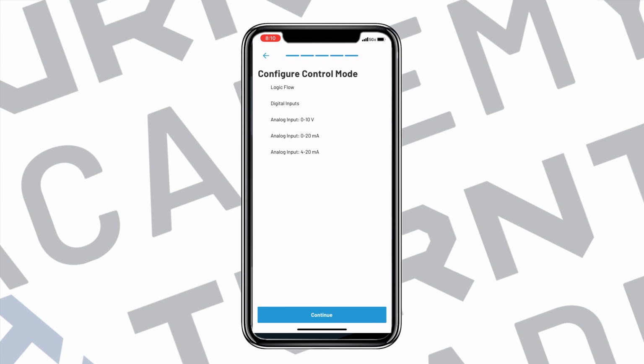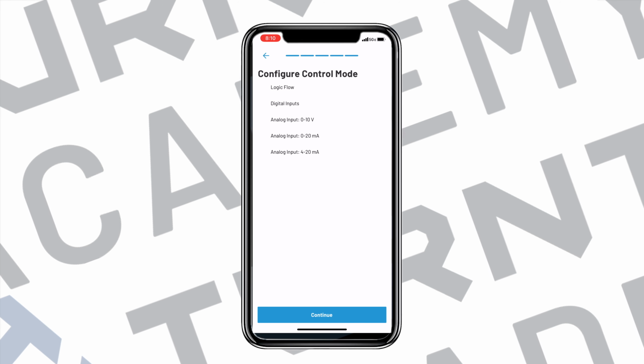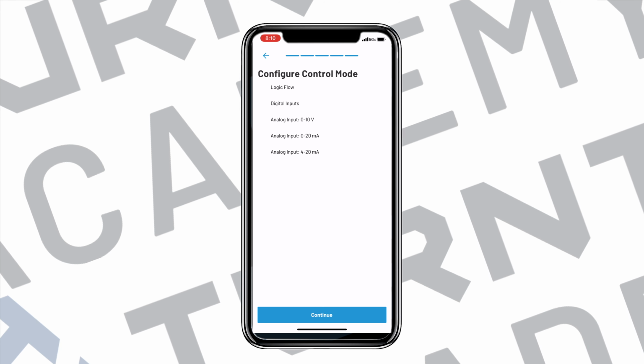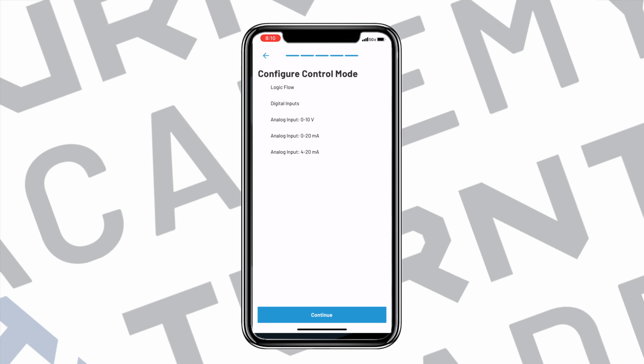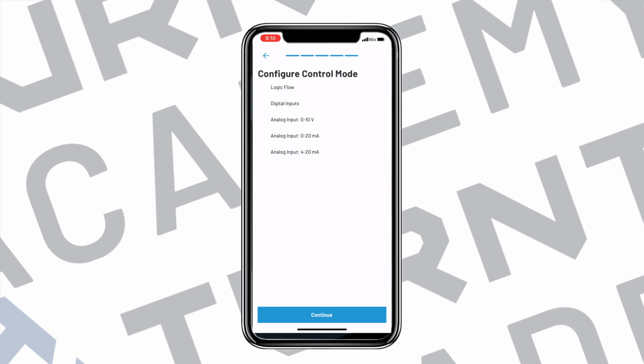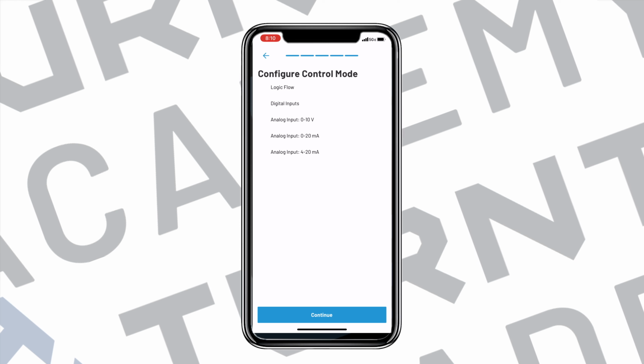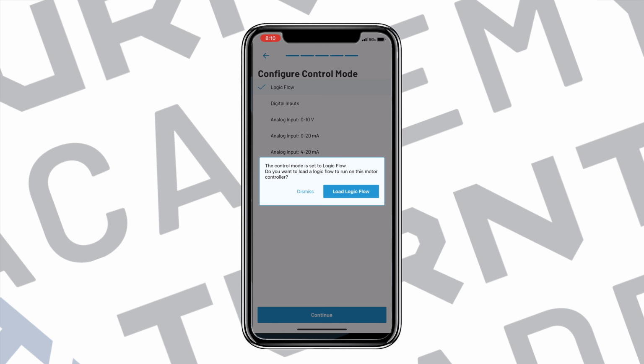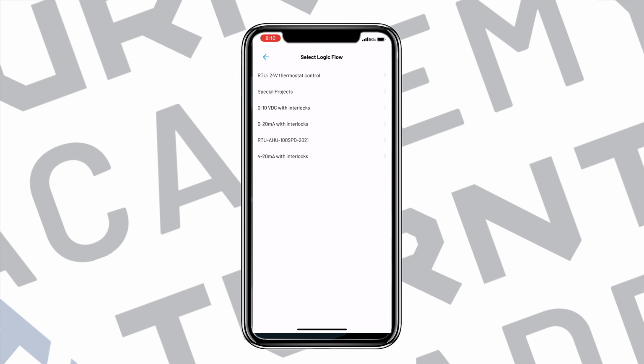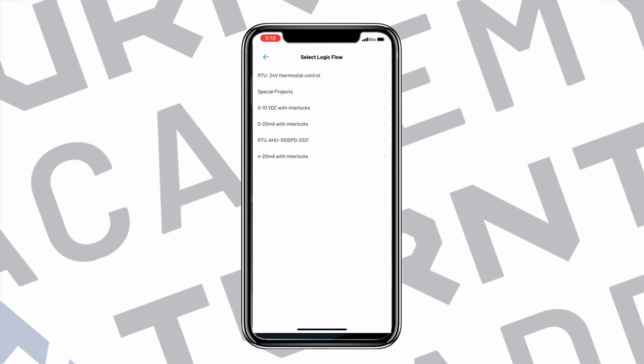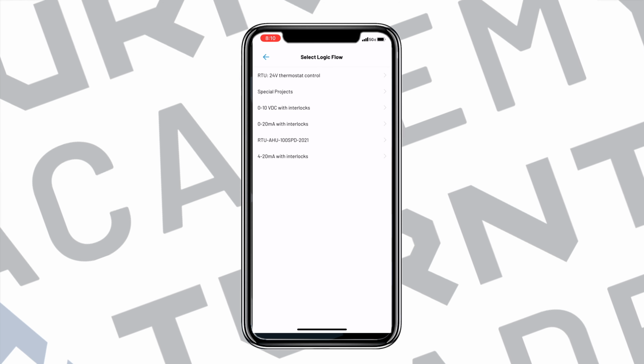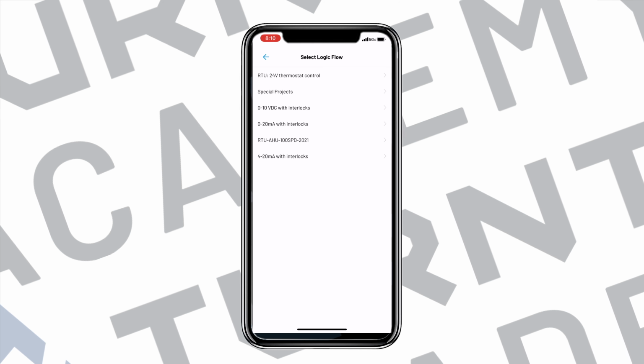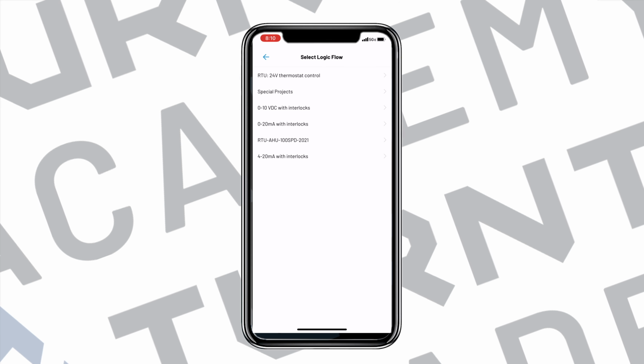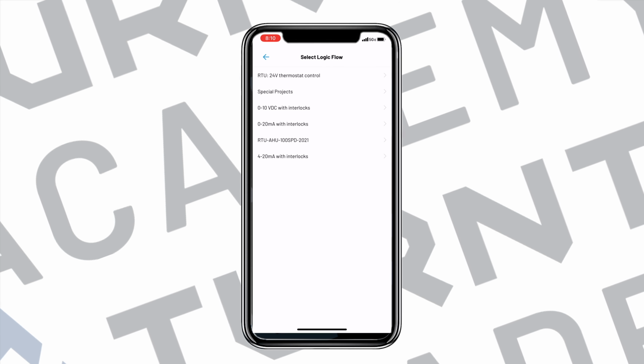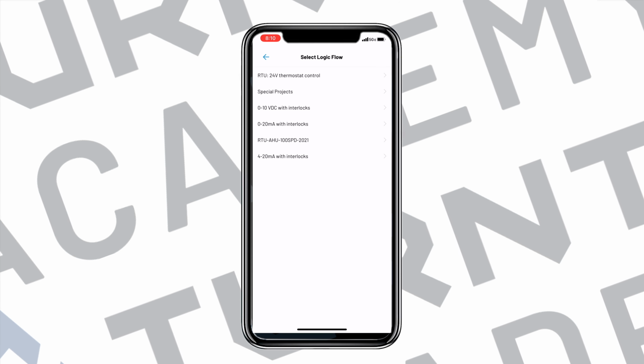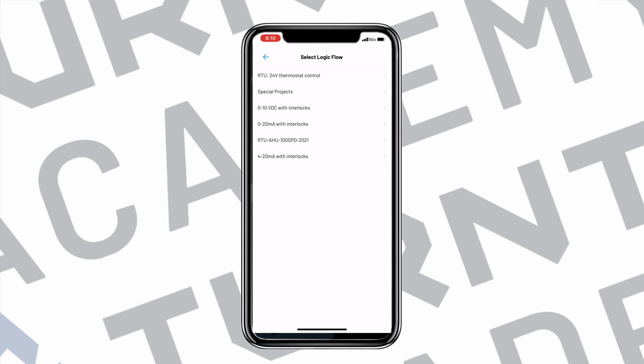Configuring the control mode is next. Logic flow is used in the majority of RTUs. Since the other modes are seldom used, they are beyond the scope of this video. Touch Logic Flow and confirm you want to load a logic flow. Since almost all RTUs use either thermostat or building management system 24-volt control, the RTU 24-volt thermostat control or special projects logic flows are used.